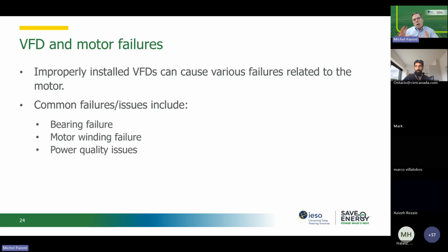So now I talked about VFDs. VFDs are great. They will provide you a lot of savings, but part of what you have to look for with VFDs is that they can also create failure points. And again, you need to address the potential issues with VFDs. Most people are aware that not all motors are VFD compatible. The motor should say inverter duty on the nameplate. If it doesn't say inverter duty, it's going to work with a VFD for a certain amount of time. Eventually, the winding will fail, and we'll explain why, but that's something that's going to happen.